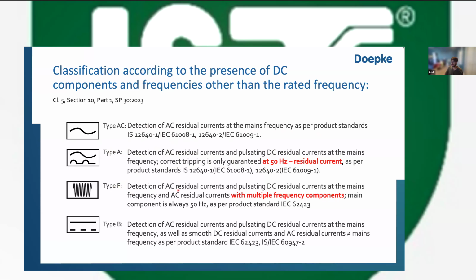Type F is a device that can handle AC and DC with some different frequency components, but the main component has to always be 50 Hz. And type B can handle DC and other frequencies. The first thing that I want to bring to your attention is that the type AC RCD is predominantly what is used generally in India.